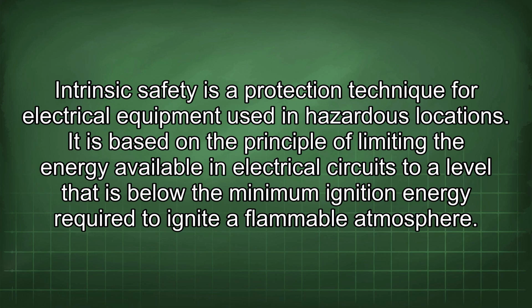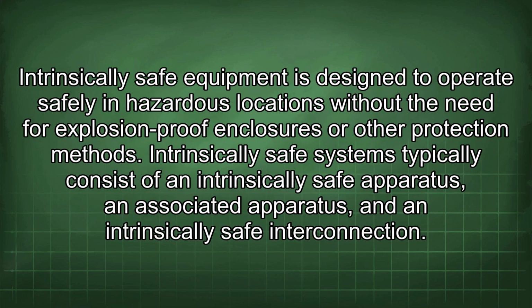Intrinsic safety is a protection technique for electrical equipment used in hazardous locations. It is based on the principle of limiting the energy available in electrical circuits to a level that is below the minimum ignition energy required to ignite a flammable atmosphere. Intrinsically safe equipment is designed to operate safely in hazardous locations without the need for explosion-proof enclosures or other protection methods. Intrinsically safe systems typically consist of an intrinsically safe apparatus, an associated apparatus, and an intrinsically safe interconnection.